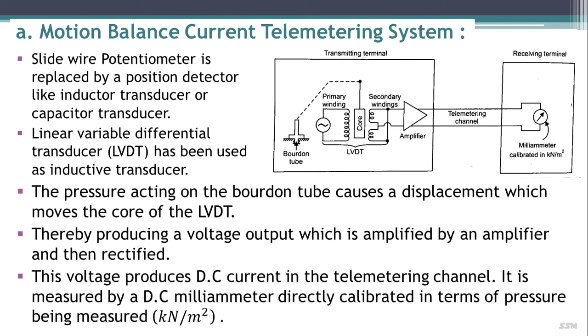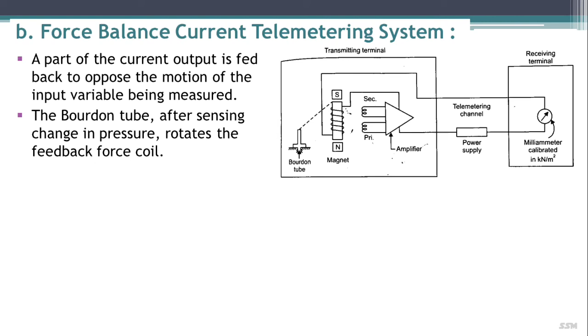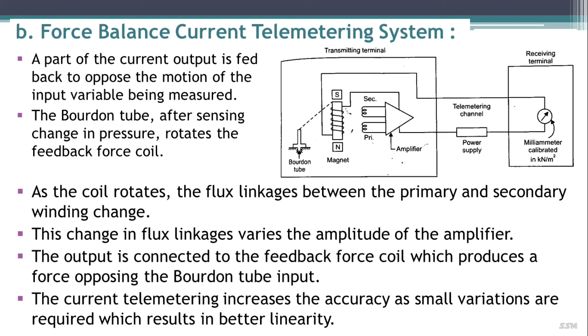Next we'll discuss the force balanced current telemetric system. In this system, a part of the current output is fed back to oppose the motion of the input variable being measured. The diagram shows a force balanced current telemetric system. The Bourdon tube, after sensing the change in pressure, rotates the feedback force coil. As the coil rotates, the flux linkage between the primary and secondary winding changes. This change in flux linkage varies the amplitude of the amplifier. The output is connected to the feedback force coil, which produces a force opposing the Bourdon tube input. This system of current telemetry increases the accuracy, as small variations are required, which results in better linearity.